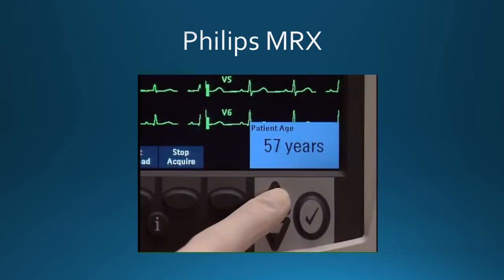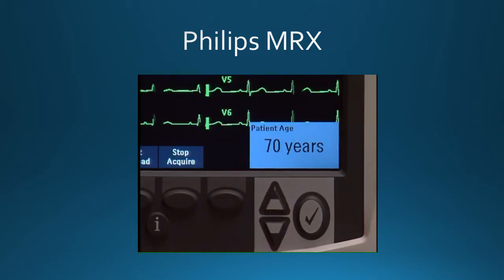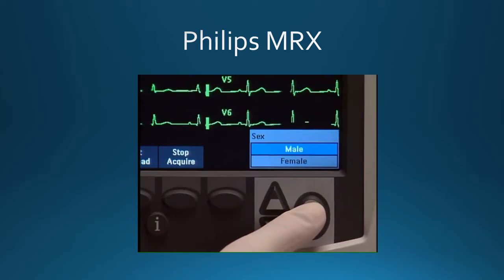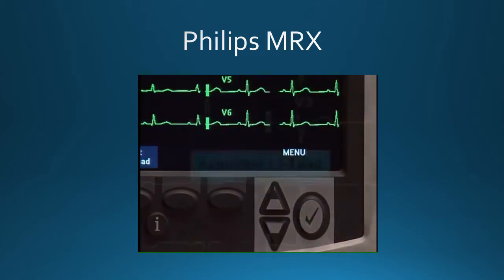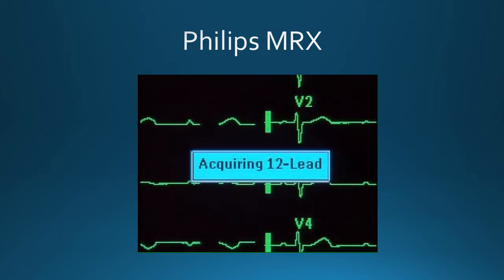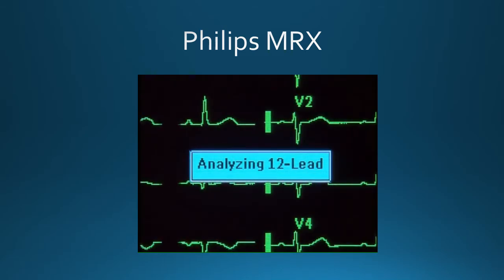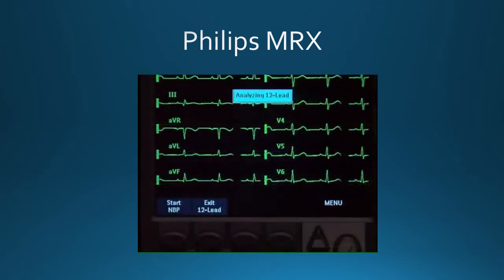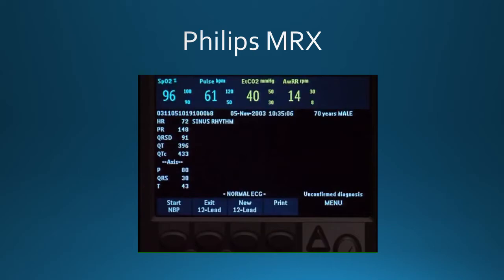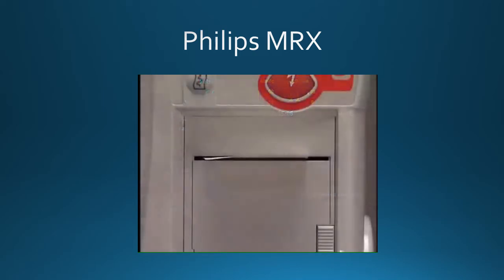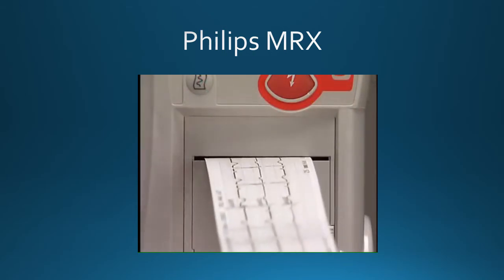The MRX prompts you to enter the patient's age and sex. This information is required to correctly analyze the 12 lead. After entering the required information, ECG acquisition takes place. This is followed by ECG data analysis. Upon completion of analysis, the 12-lead report screen displays. The MRX then automatically prints an interpretive 12-lead report based on the configured analysis setting.